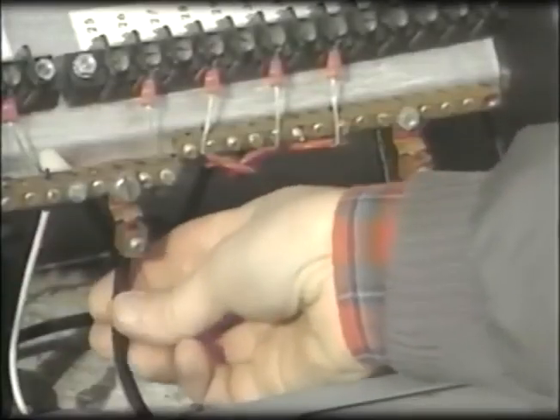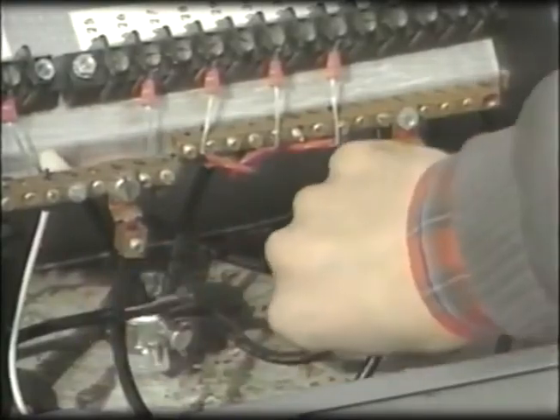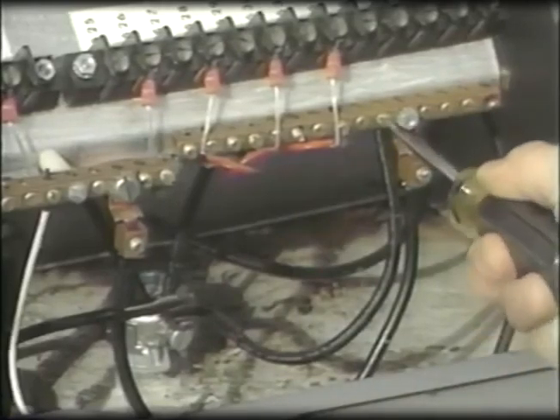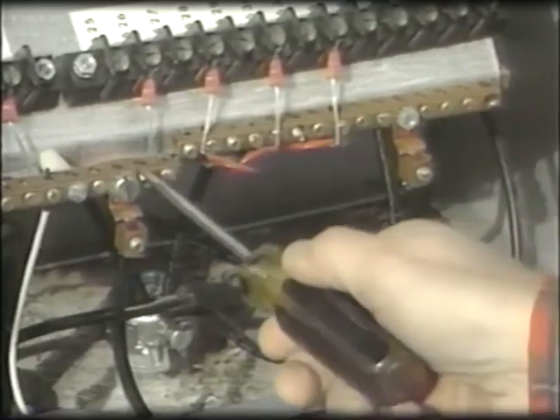Temperature changes loosen wires, so test for loose bonds, particularly where bolts or screws are used. Pay attention to bonds and grounding conductors. If the ground rod connection is bolted, be sure to check it for corrosion and loosening. When your maintenance check is complete, replace the damaged components, clean and tighten the connection.